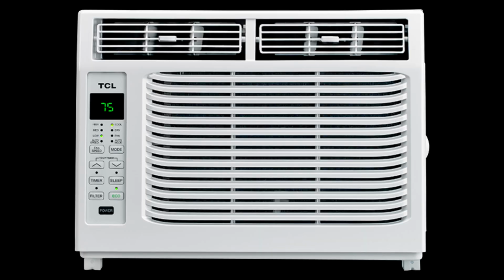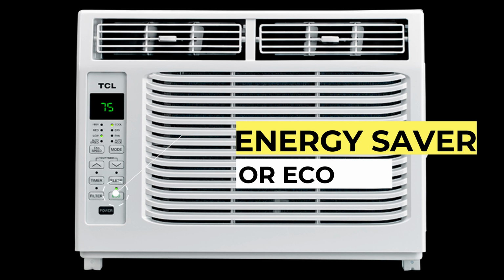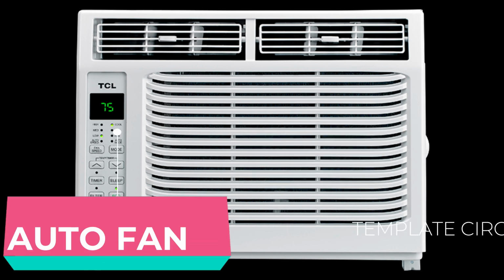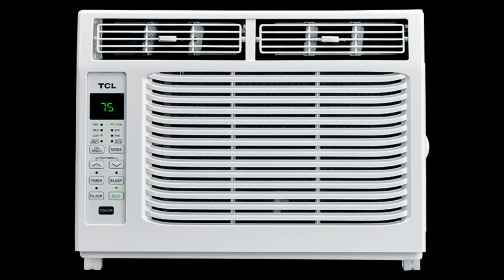It also causes extra wear on the fan motor and compressor because it's cycling them on and off all the time. Something else that you need to be aware of about these energy efficient modes is a lot of the times they're broken up into two settings. The energy saver or eco setting and the automatic fan setting. You need to make sure that both auto fan and energy saver modes are off.